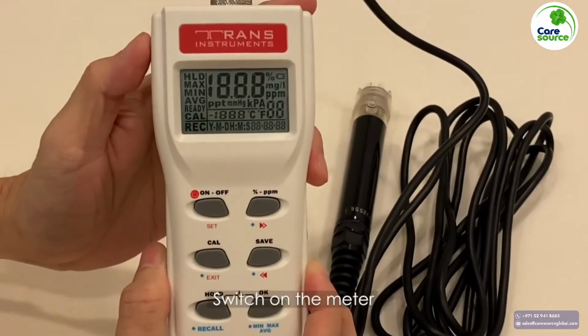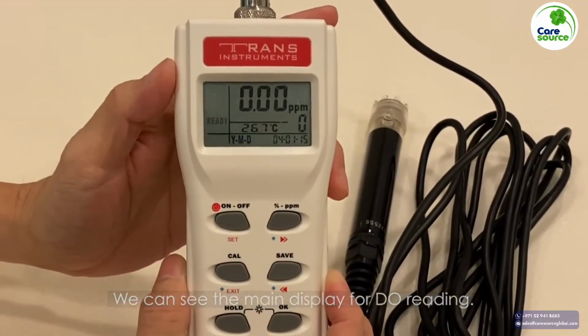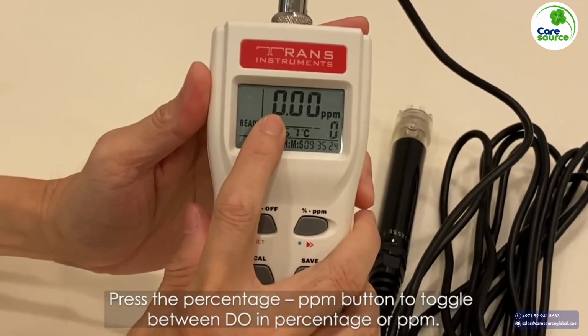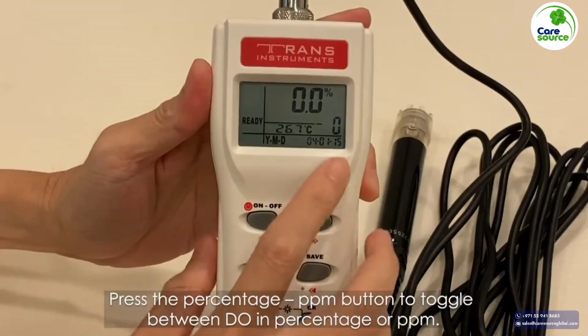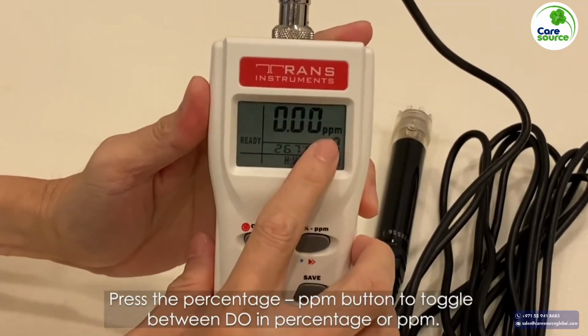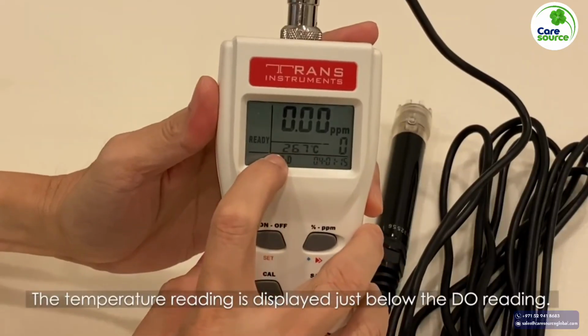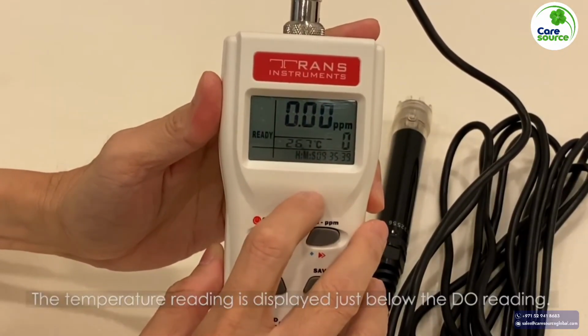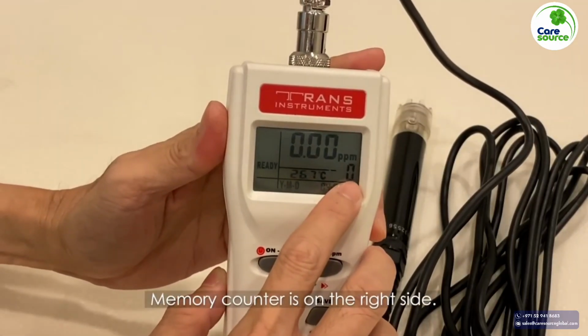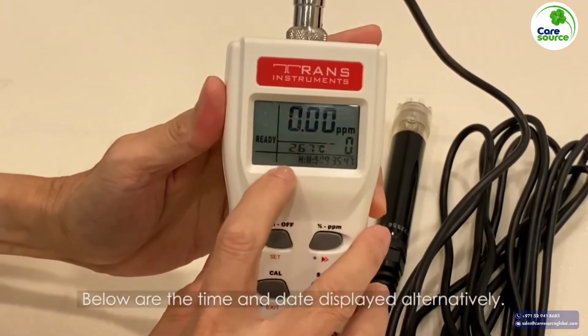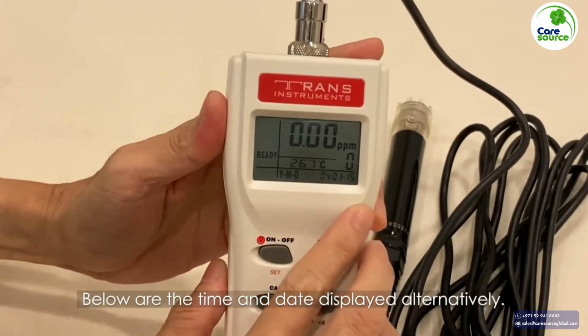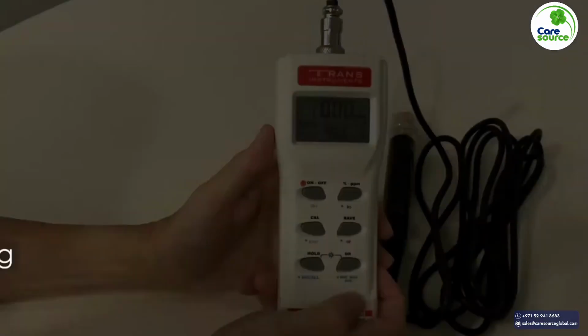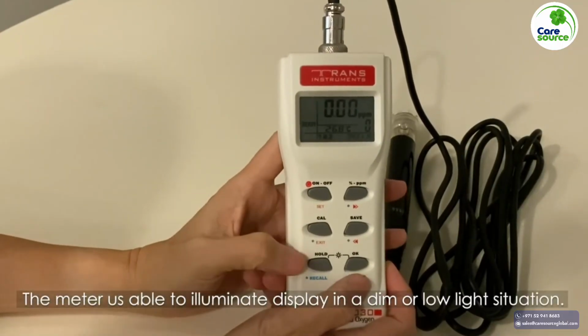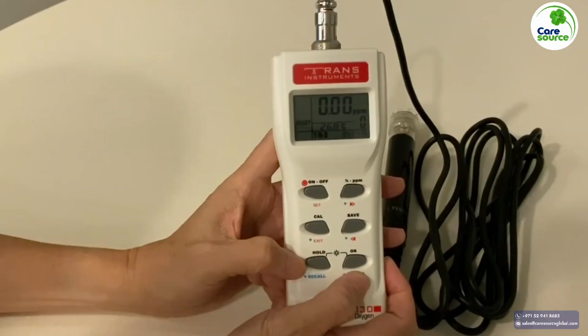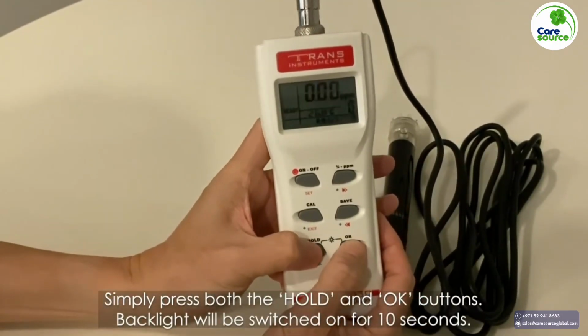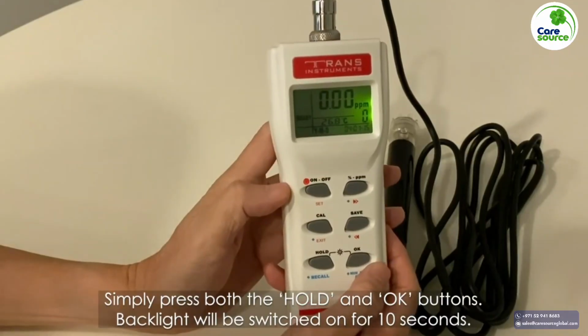Switch on the meter. We can see the main display for DO reading. Press the percentage ppm button to toggle between DO in percentage or ppm. The temperature reading is displayed just below the DO reading. Memory counter is on the right side. Below are the time and date, displayed alternately. The meter is able to illuminate the display in dim or low light situations. Simply press both the hold and OK buttons and the backlight will be switched on for 10 seconds.